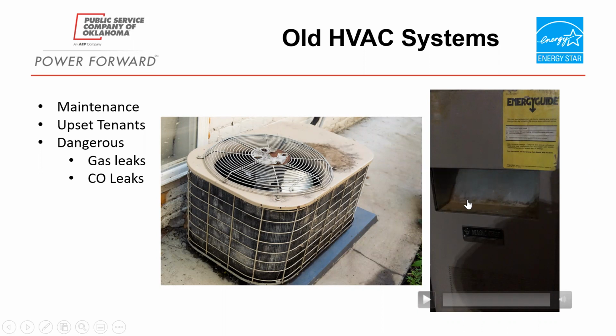What happens is the coil, or the heat exchanger, inside these units can potentially crack or break and rust through. And if that happens, then carbon monoxide not only goes out the flue, but it also penetrates in through the ductwork and is distributed throughout the house, which is a very, very dangerous thing. So we want to make sure that all that stuff is replaced, and let us get some money for you on those too.